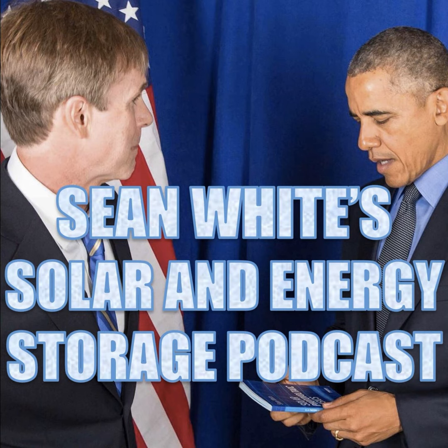Also, a lot of times when you see a big long list of things, there's going to be something that's other. And so if you're connecting to other energy sources, you go to Article 705. 705 is a big part of energy storage systems. That's interconnected power production sources. And then, last but not least, especially if you're all alone working off-grid, is standalone operation, where the output of an energy storage system is capable of operating in standalone mode. So that could be your backup system for when the grid goes down. Then the requirements of Article 710.15 apply. Article 710 is standalone systems. And there are some special requirements that were also stolen from 690.10 in the 2014 National Electrical Code. Then they made their own very short article on standalone systems.